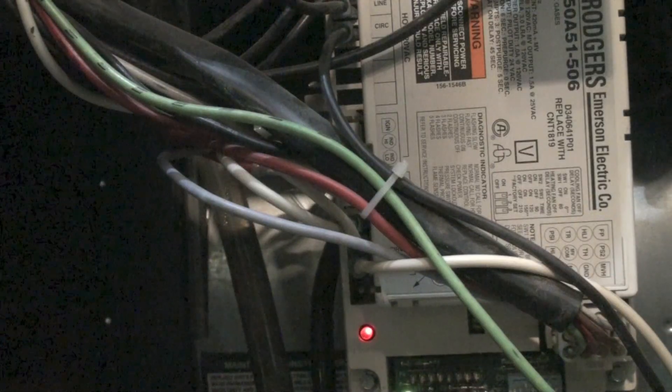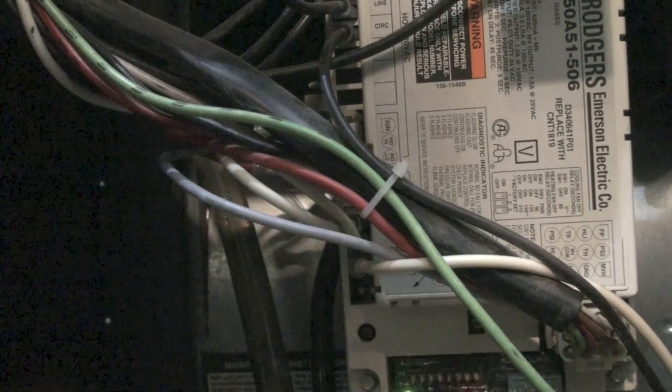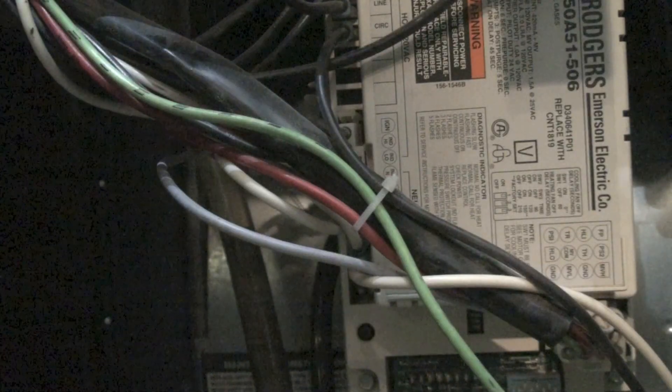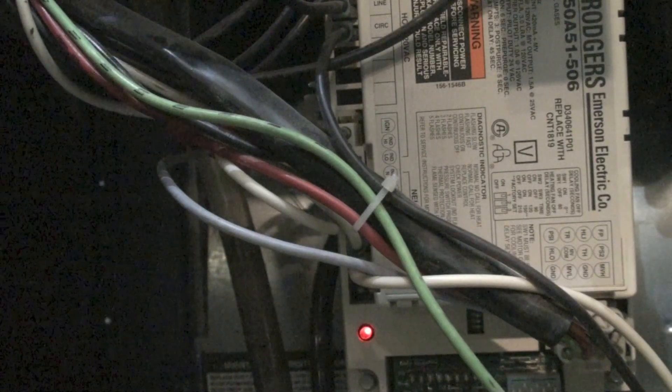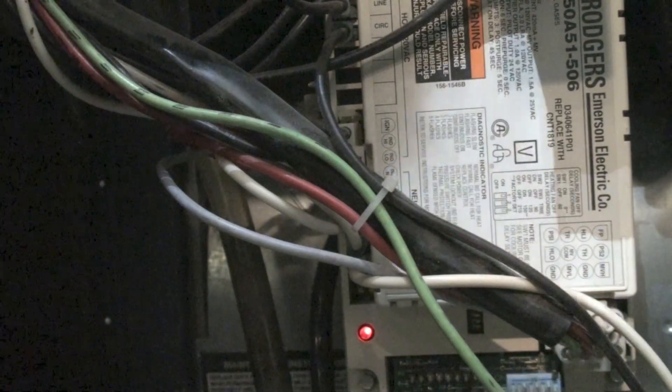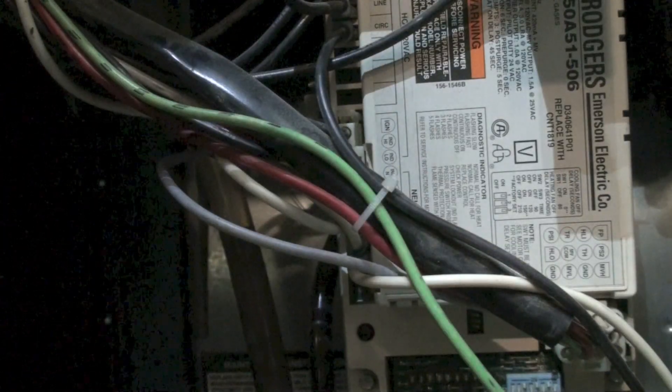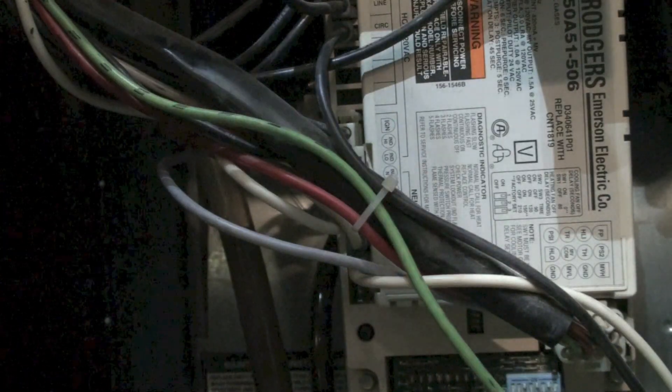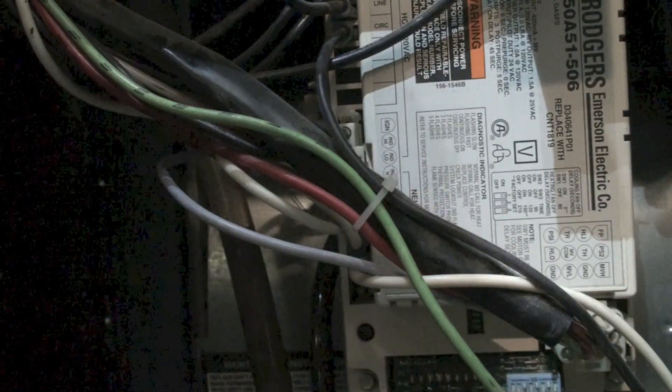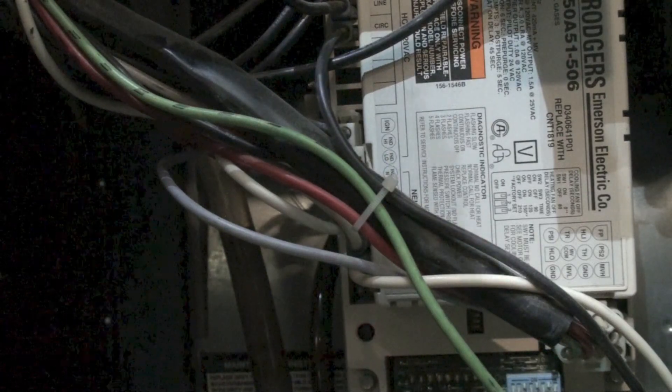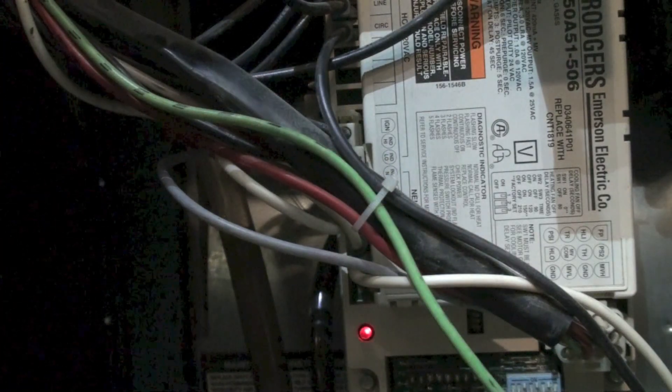This is a three blink code. That's a pressure switch failure. Now it's not telling you that it's a pressure switch problem, it's telling you it's a vacuum problem. Most of these things don't give you accurate ideas of what has actually happened to the furnace, they give you a place to look.